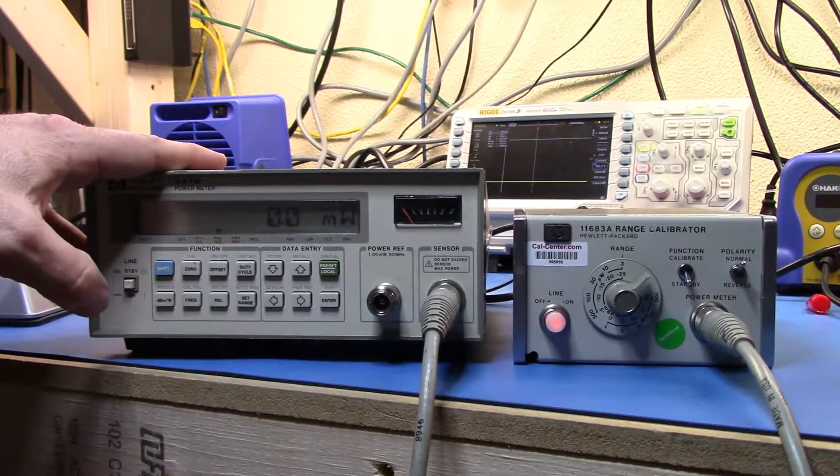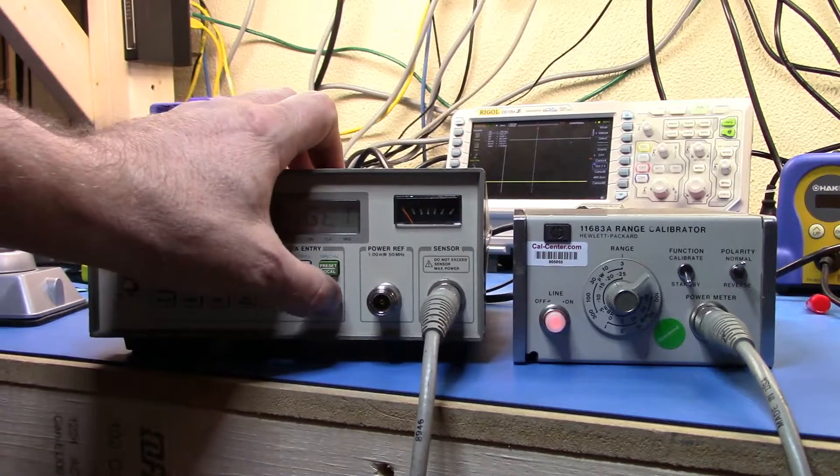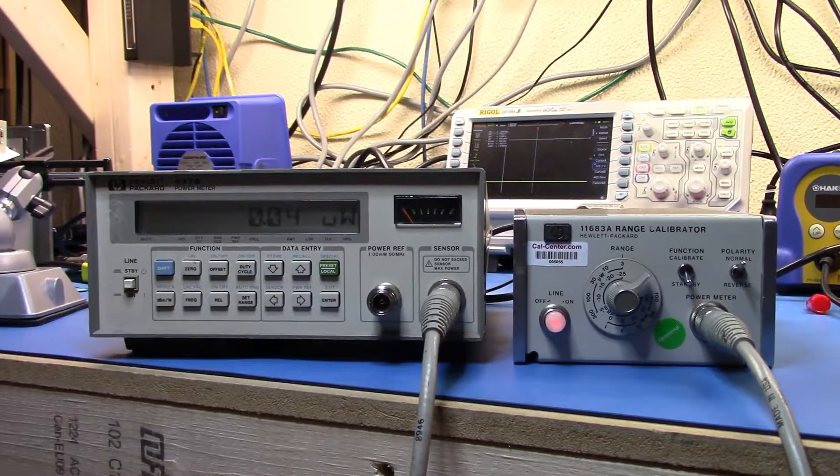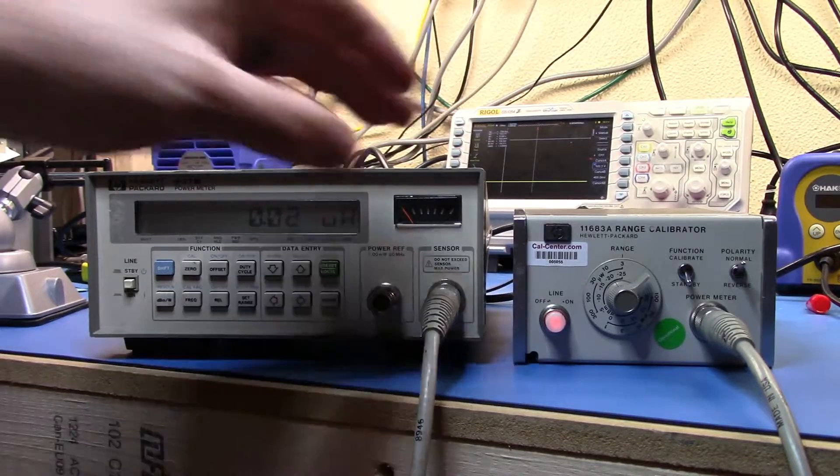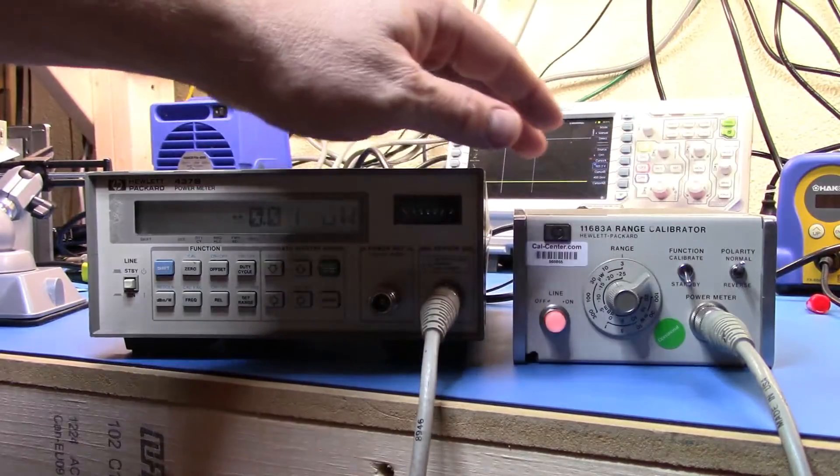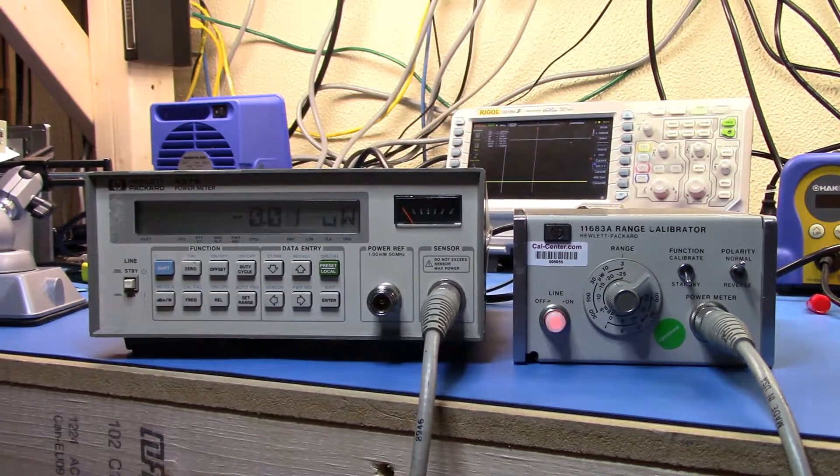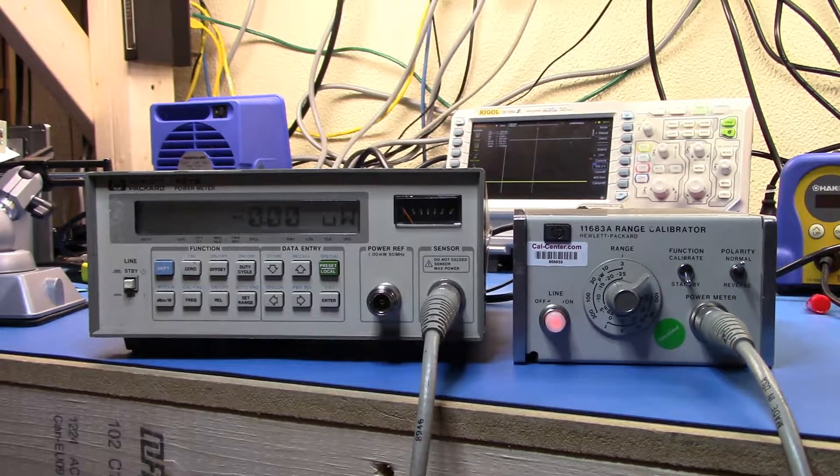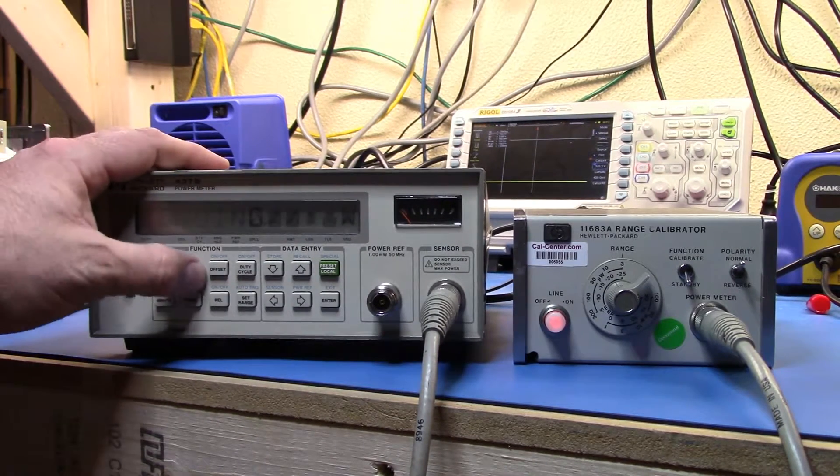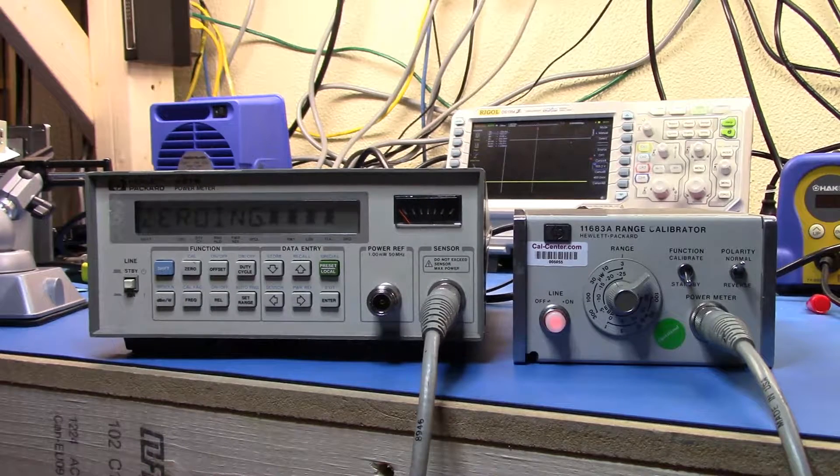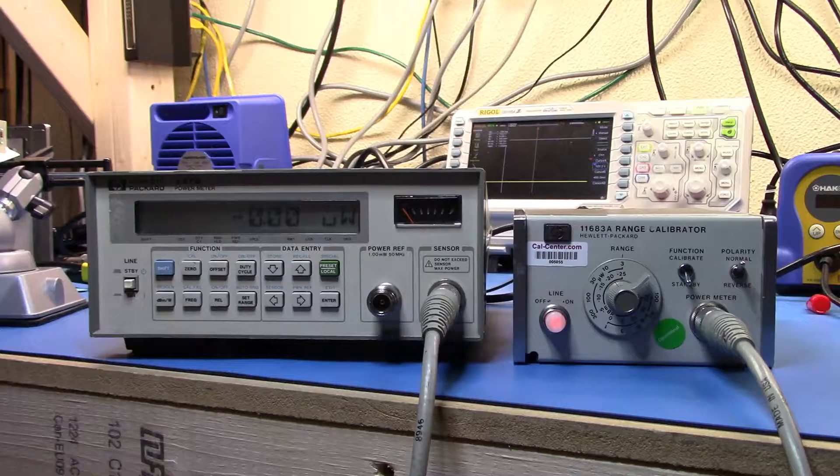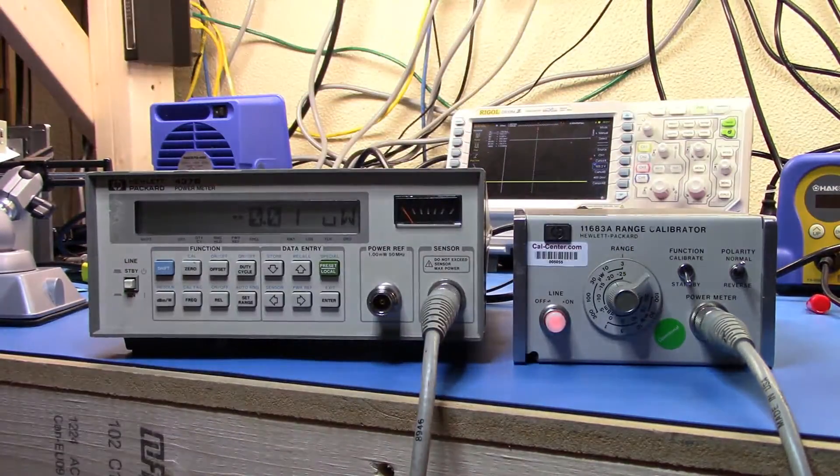So we have the meter turned on, we set preset local, we set dB milliwatts, range function is going to be standby, polarity is normal, range is 3 microwatts, line is on, press the power meter zero function.